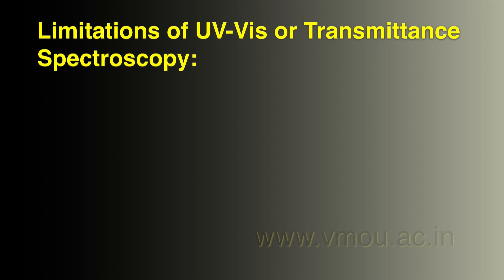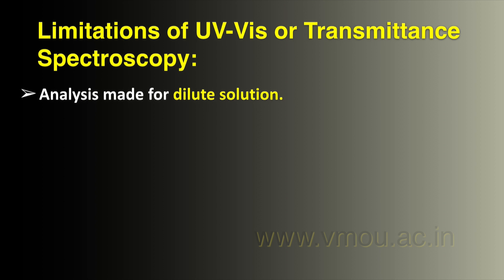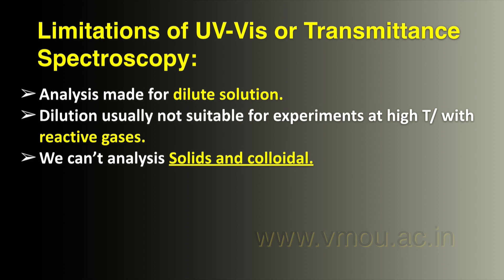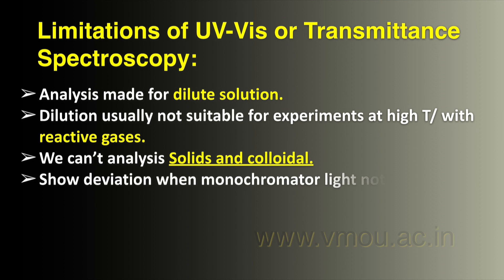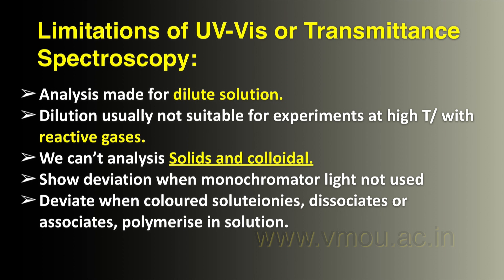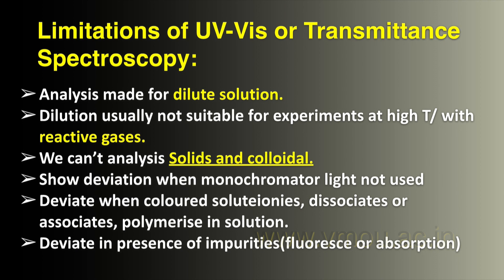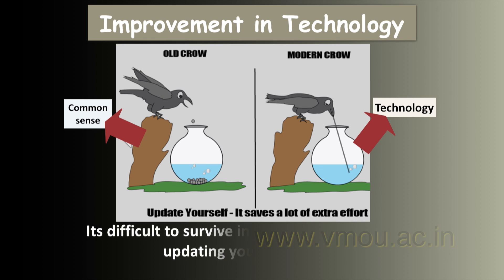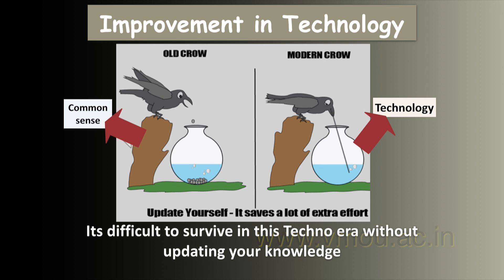These are limitations of UV-visible transmittance spectroscopy. The analysis is made for dilute solutions only, and it is not suitable for experiments at high temperature or with very reactive gases. We cannot analyze solid and colloidal samples with this technique. It can show deviation when non-monochromatic light is used, or when a colored solution ionizes, dissociates, associates, or polymerizes. It can also deviate in the presence of impurities due to fluorescence. So we need to improve the technology, and it is difficult to remain current without updating our knowledge.